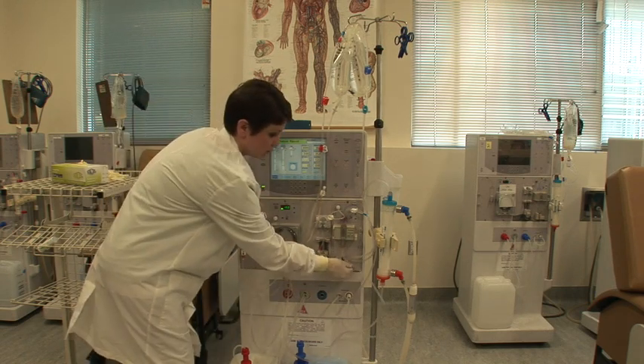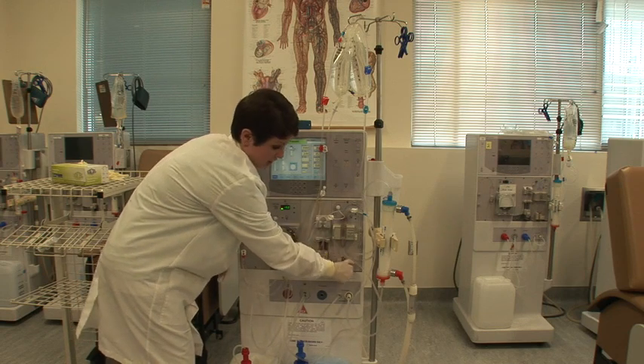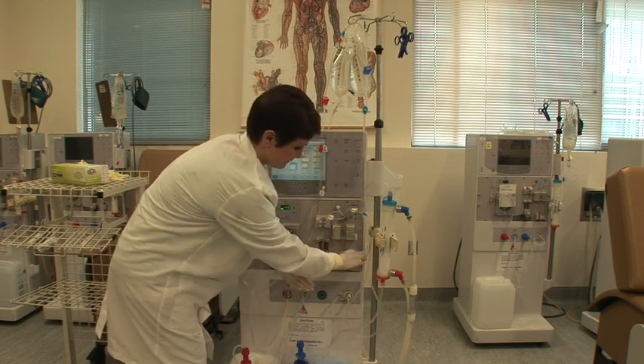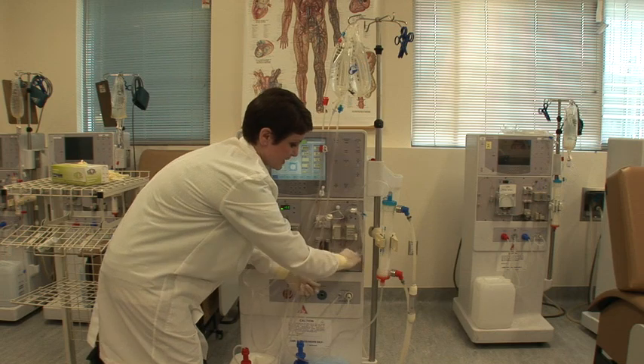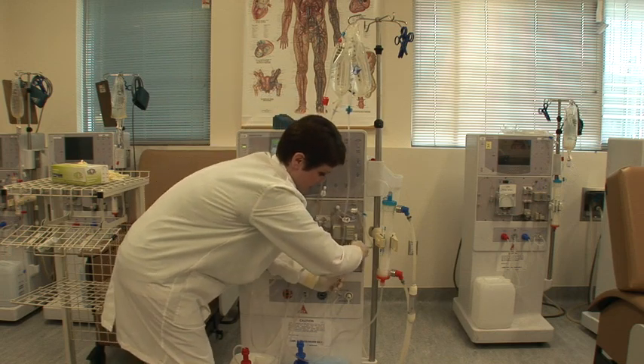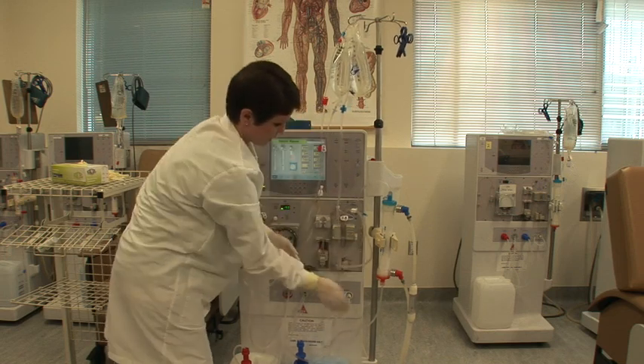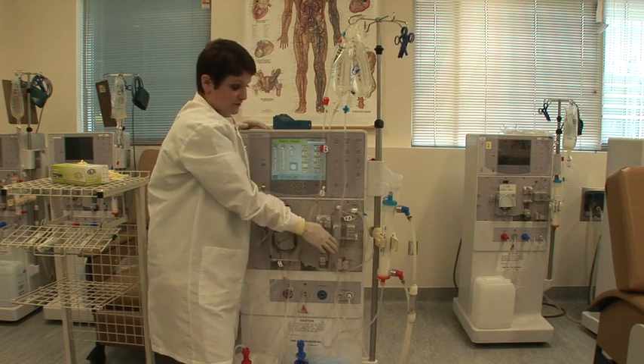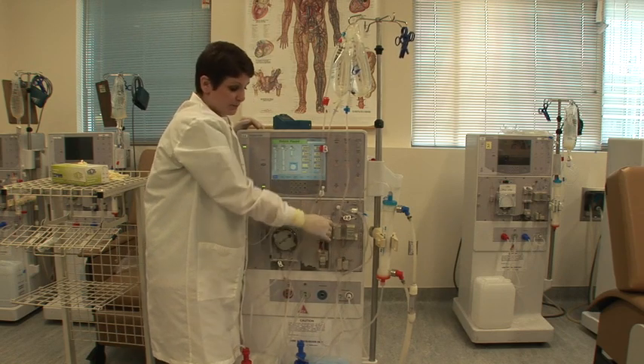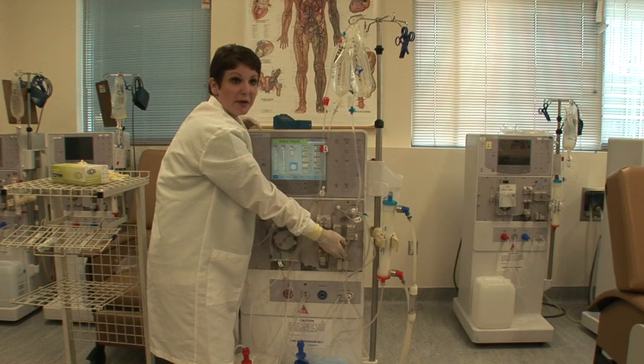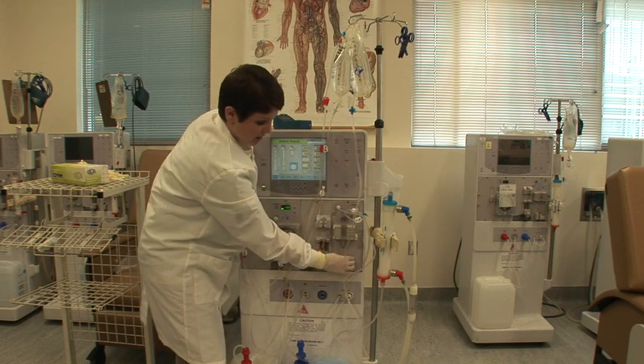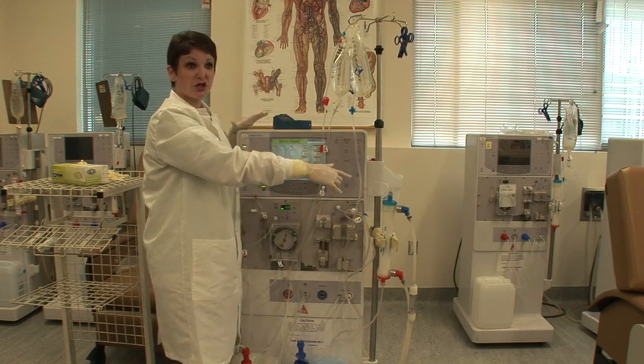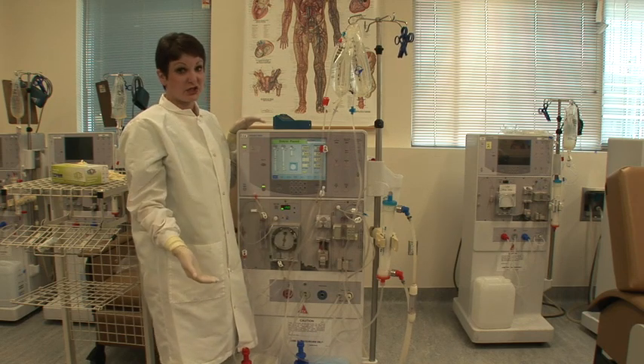You're also going to arm your air lock. So you're going to open this door, hold down that little metal bar, and thread that guy in there. And what that's going to do is if there's any air detected in the venous chamber, that's going to completely stop flow back to the patient. So it'll clamp it off there and nothing will get returned to the patient, so that if there's air in there, the patient doesn't get an air embolism.